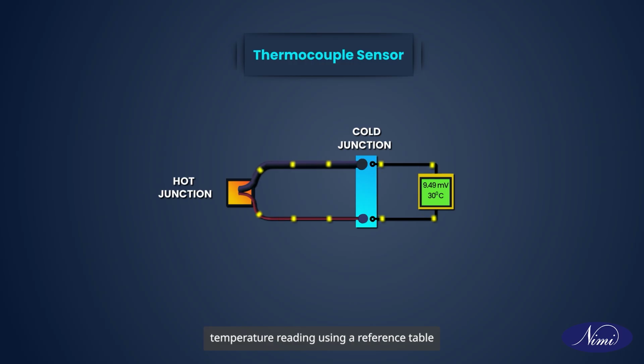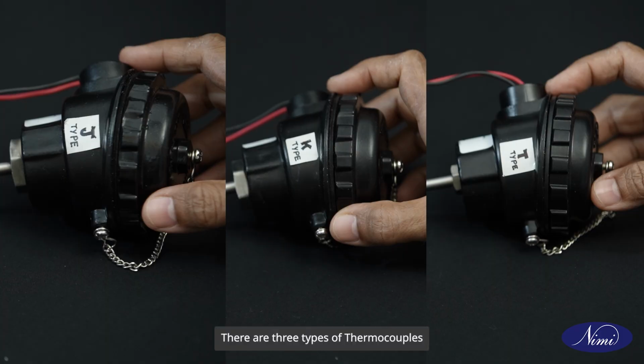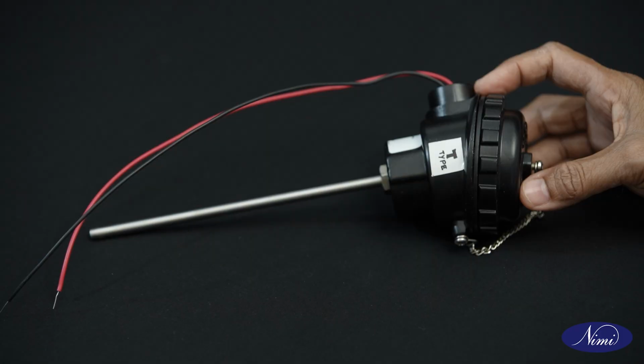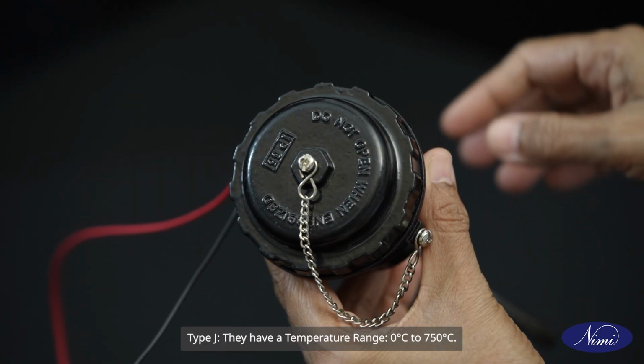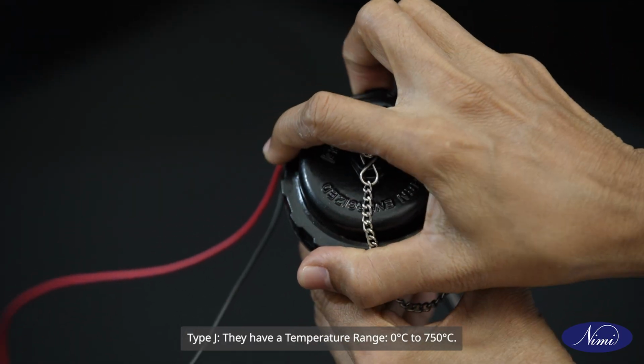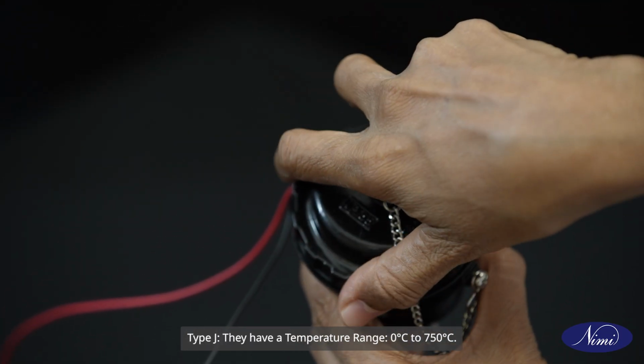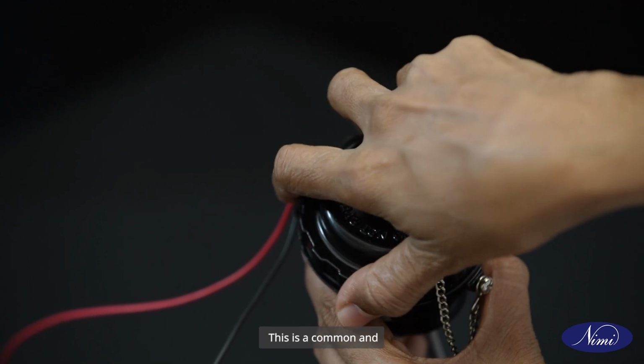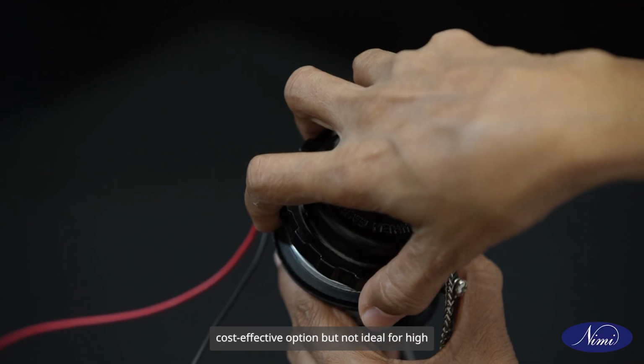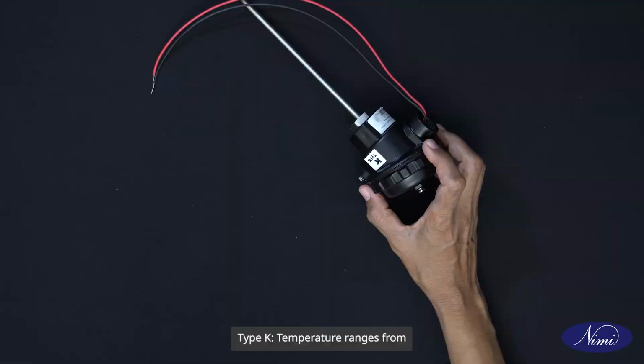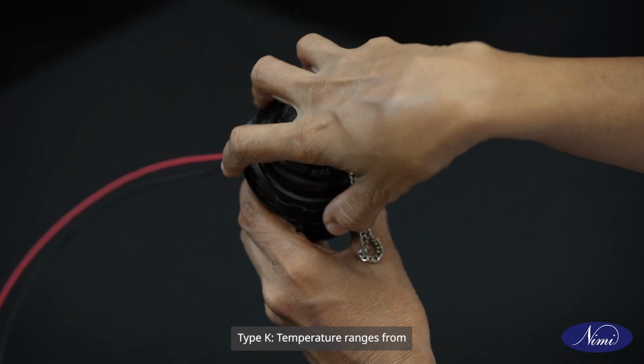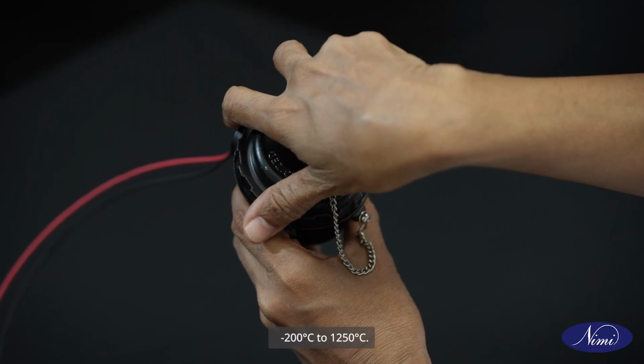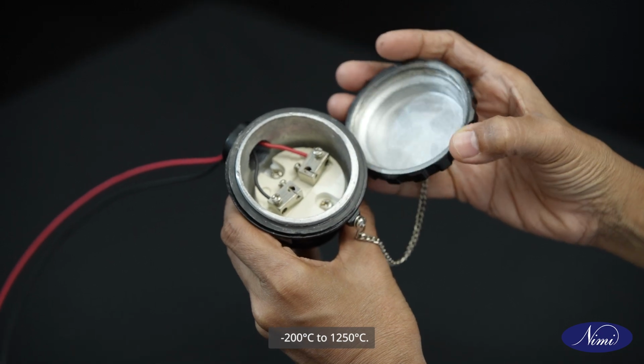using a reference table. There are three types of thermocouples: type J, type K, and type T. Type J has a temperature range from 0 degrees Celsius to 750 degrees Celsius. This is a common and cost-effective option but not ideal for high temperatures. Type K has a temperature range from minus 200 degrees Celsius to 1250 degrees Celsius.